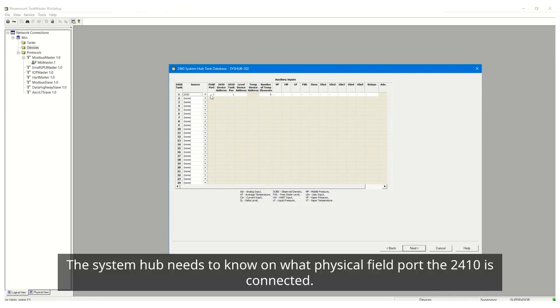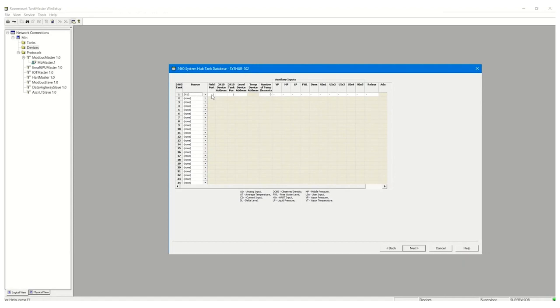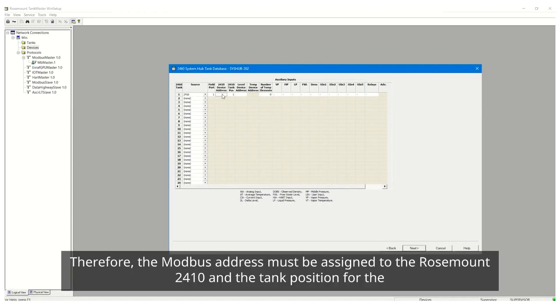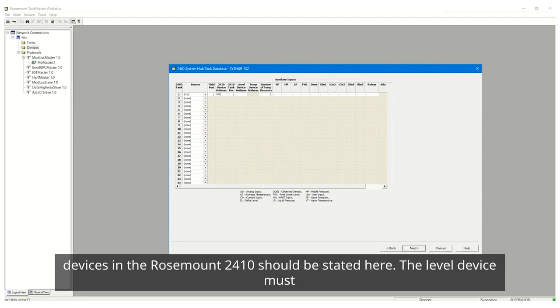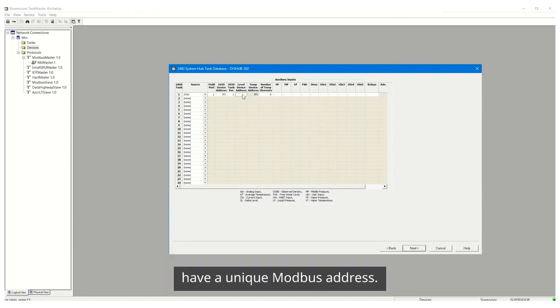The System Hub needs to know on what physical field port the 2410 is connected. Therefore, the Modbus address must be assigned to the Rosemount 2410 and the tank position for the devices in the Rosemount 2410 should be stated here. The level device must have a unique Modbus address.